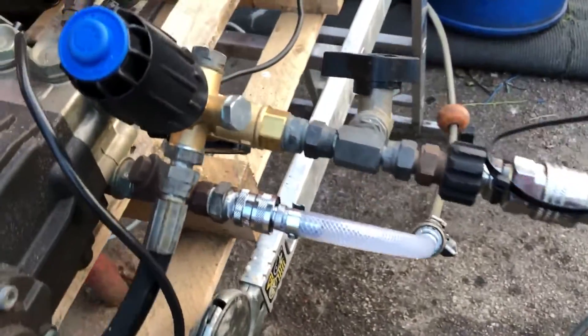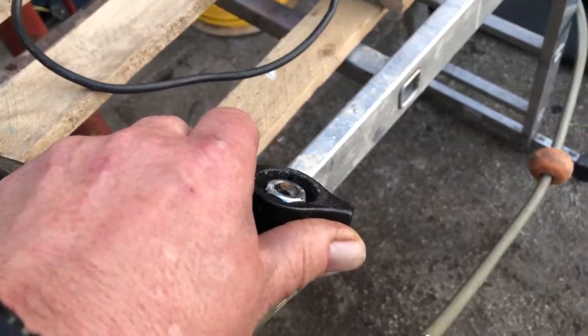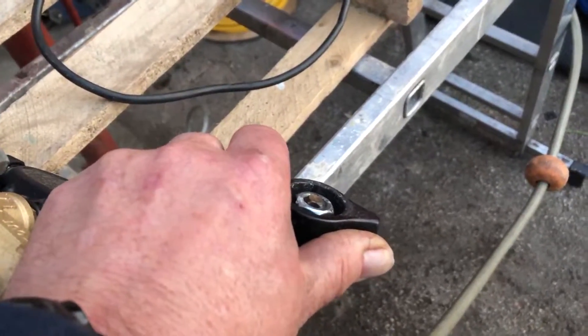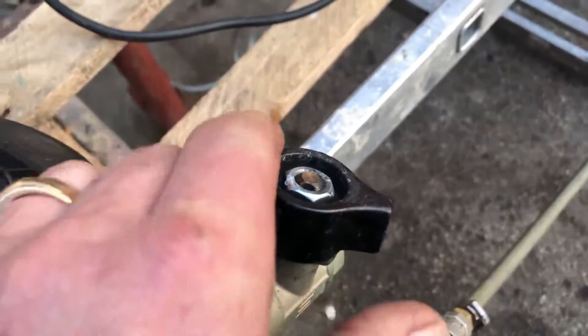What we're going to do is make the machine appear as if it's got a leak, and you'll hear what happens. We're going to make it leak as though the gun's leaking slightly, and the machine will jump — you'll see it jump every time. This is a slight leak we've caused on the machine.